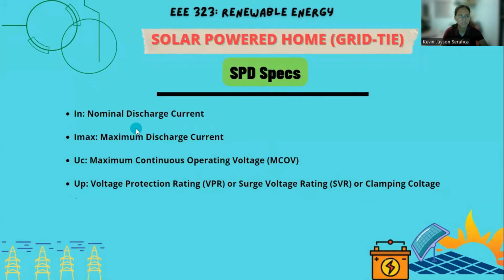So, punta naman tayo sa SPD specs. IN stands for nominal discharge current, IMAX, maximum discharge current, UC, maximum continuous operating voltage or MCOV. So ito yung tinitingnan natin sa ating SPD. Sa next is UP, voltage protection rating or VPR, or surge voltage rating SVR or clamping voltage.